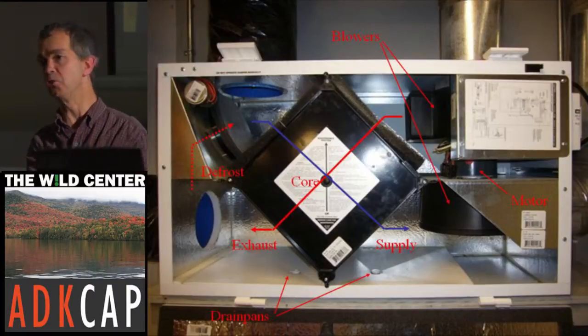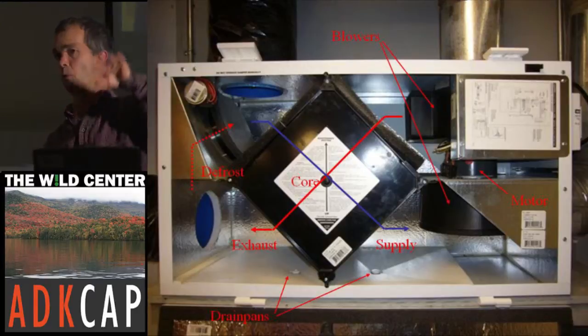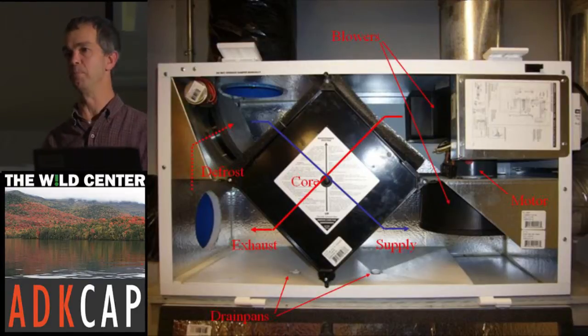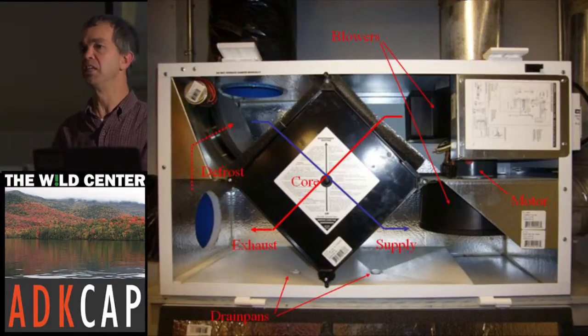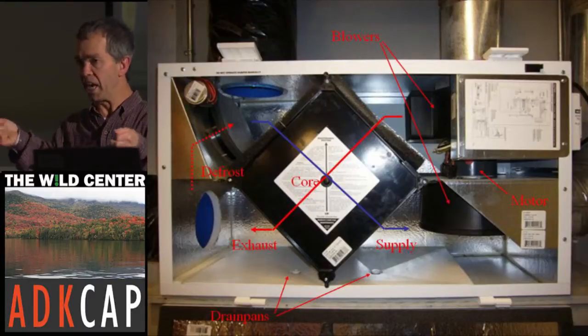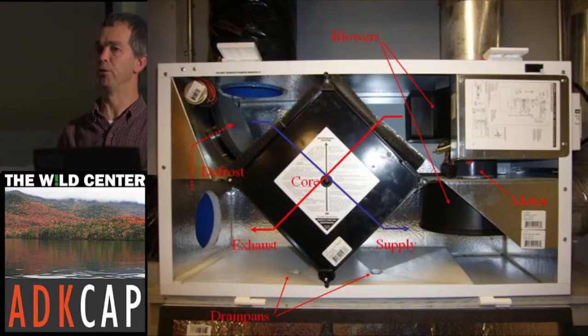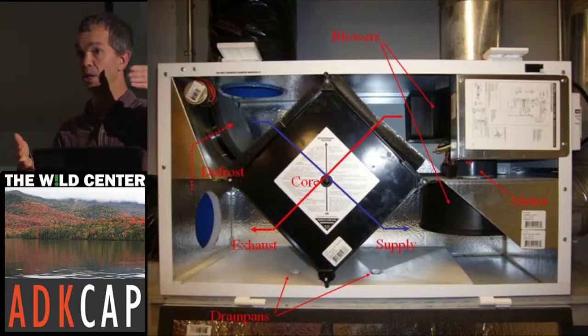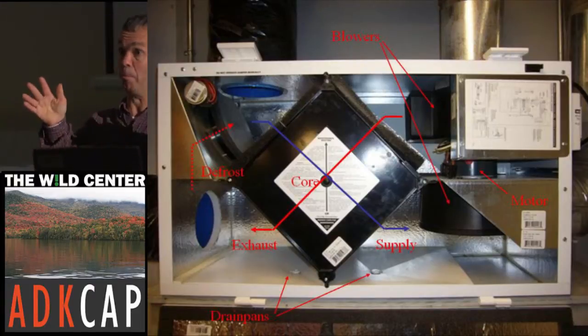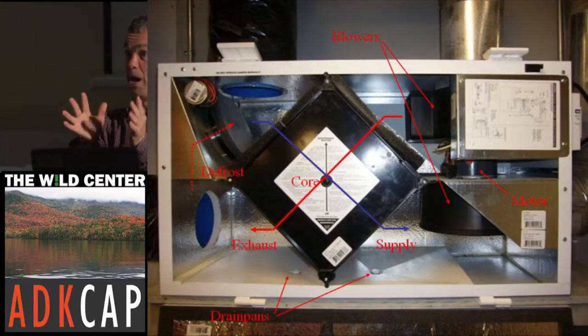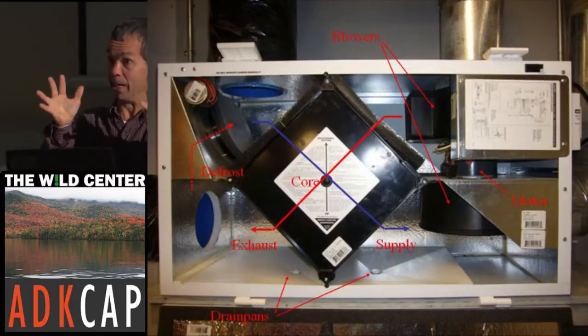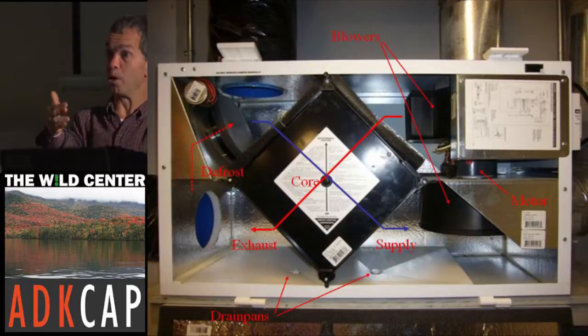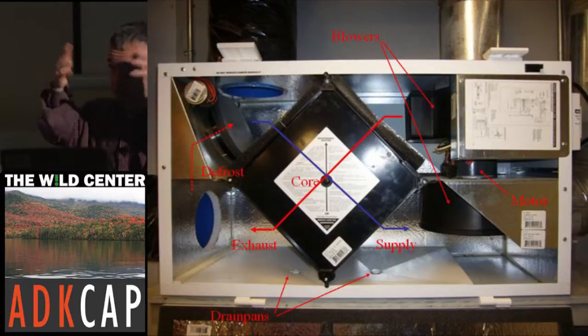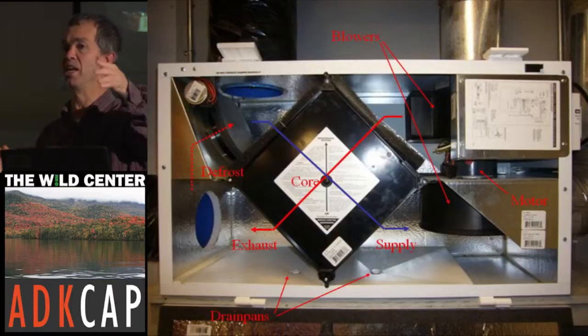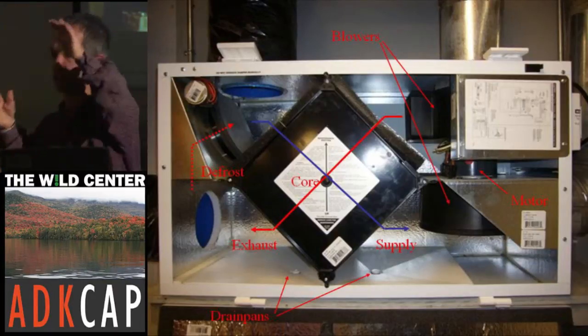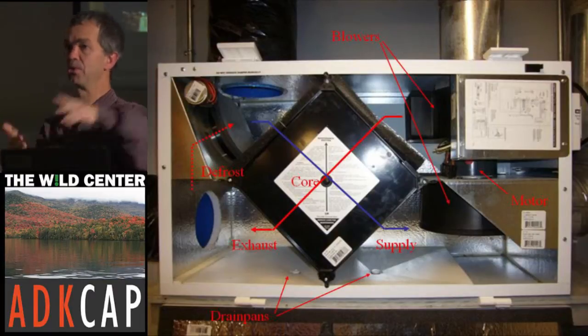Yeah, you've got to balance it. You can't just put one of these up and throw a couple of ports in the kitchen and a couple elsewhere—it's fairly easy to balance. There's a gauge, you run it, you test the airflow, and basically you want to deliver a certain amount of CFM. Remember, you've reduced the leakage of the house a lot, so you're living in a pretty tight box. What you're trying to do is bring in enough air for the occupants. There are charts based on how many people you have, how many dogs, if you have plants, and so on.